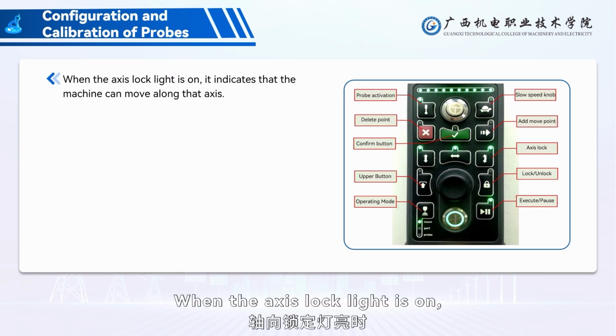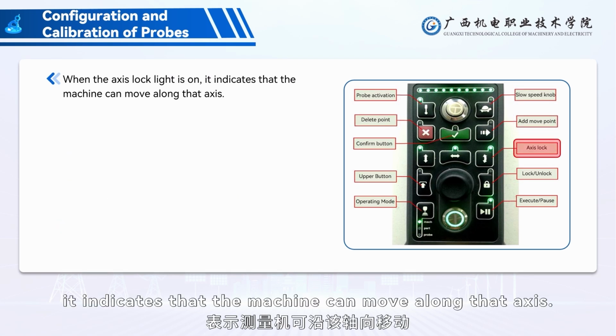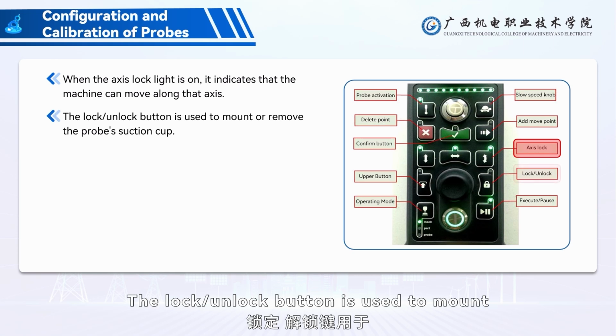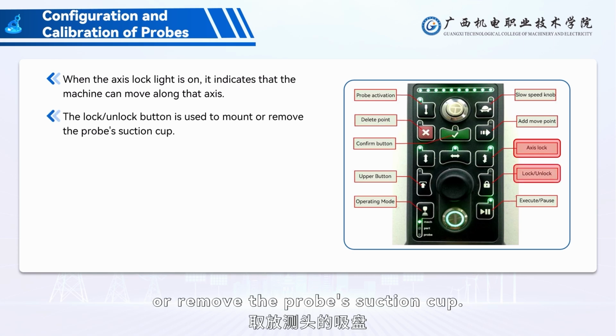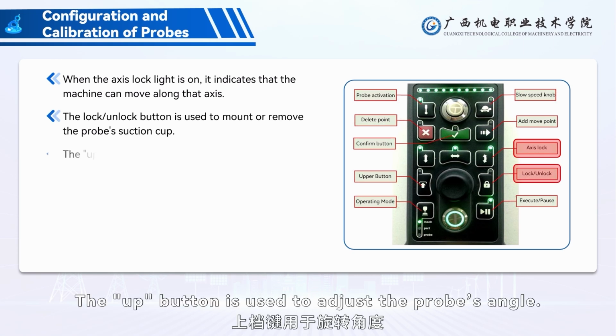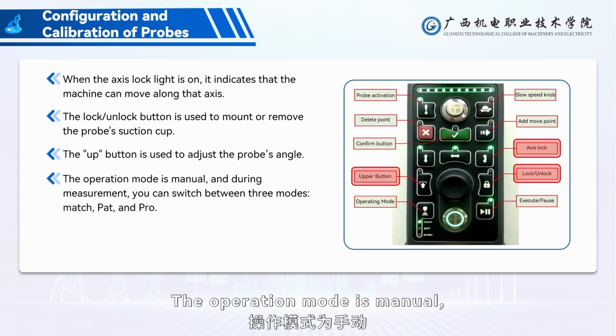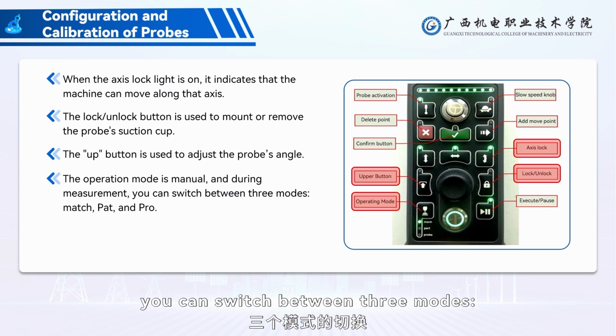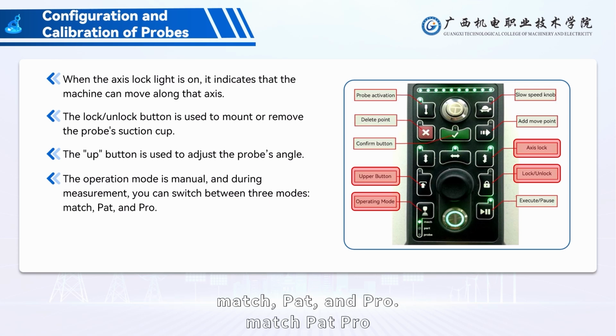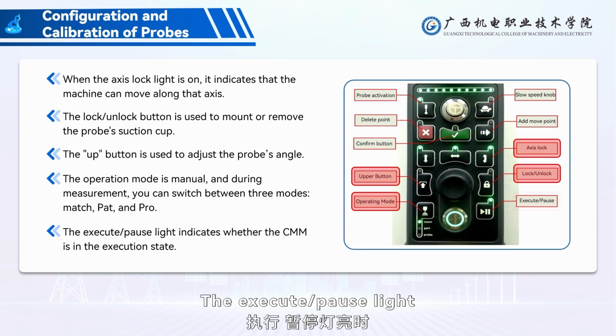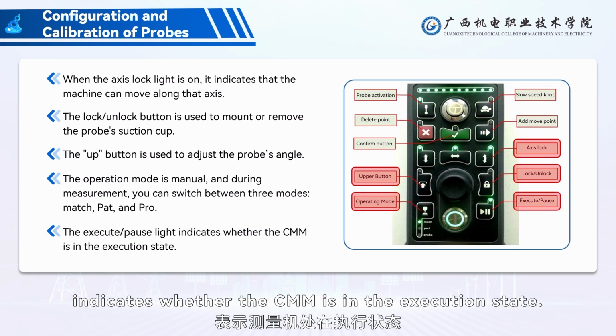When the axis lock light is on, it indicates that the machine can move along that axis. The lock/unlock button is used to mount or remove the probe suction cup. The up button is used to adjust the probe's angle. The operation mode is manual, and during measurement, you can switch between three modes: match, pat, and pro. The execute/pause light indicates whether the CMM is in the execution state.